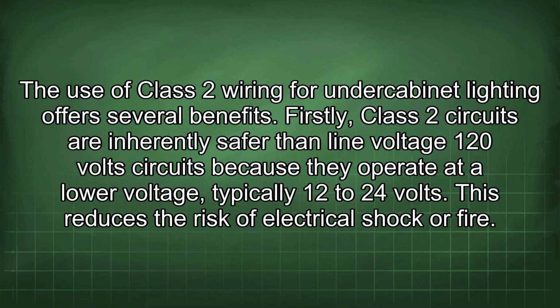The use of Class 2 wiring for under-cabinet lighting offers several benefits. Firstly, Class 2 circuits are inherently safer than line voltage 120 volts circuits because they operate at a lower voltage, typically 12 to 24 volts. This reduces the risk of electrical shock or fire.